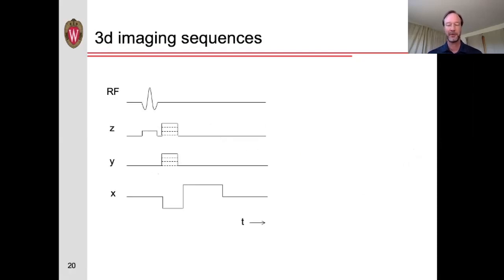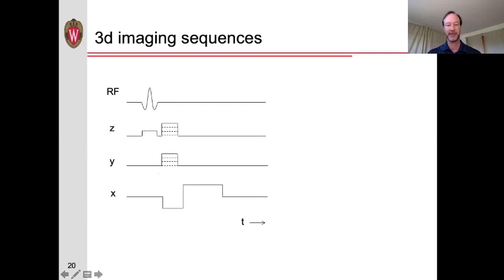We've been talking so far about 2D imaging sequences. It is also possible to collect data in 3D using additional phase encoding in the third dimension. Instead of just phase encoding in the Y direction, you also vary the phase encoding in the Z direction. Each time you excite, you're exciting not just a single slice, but rather a slab or entire brain volume, doing phase encoding in both the Y and Z directions.